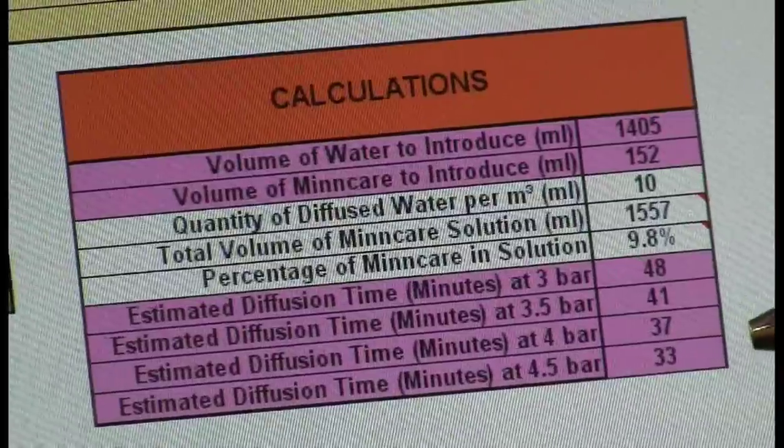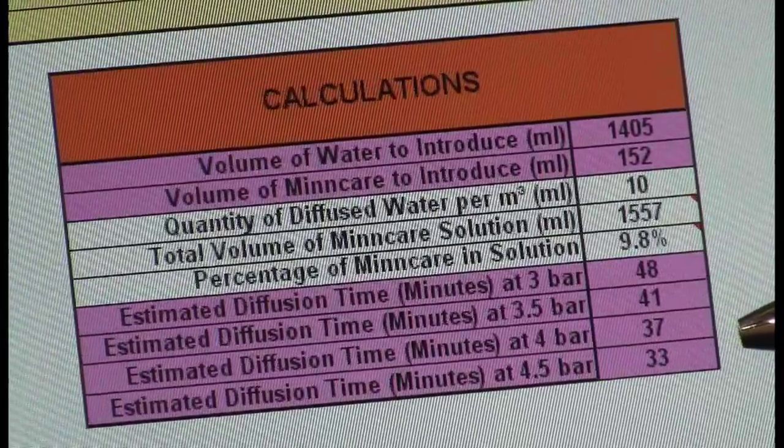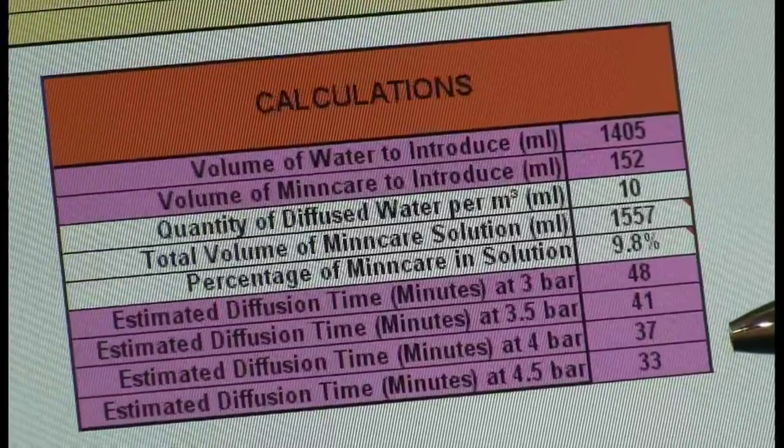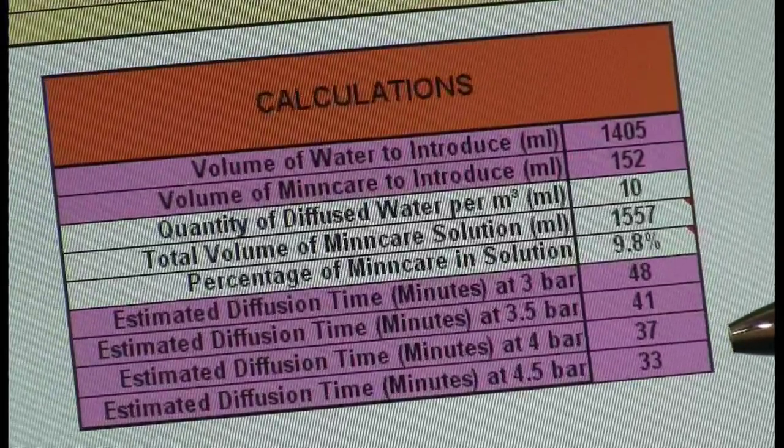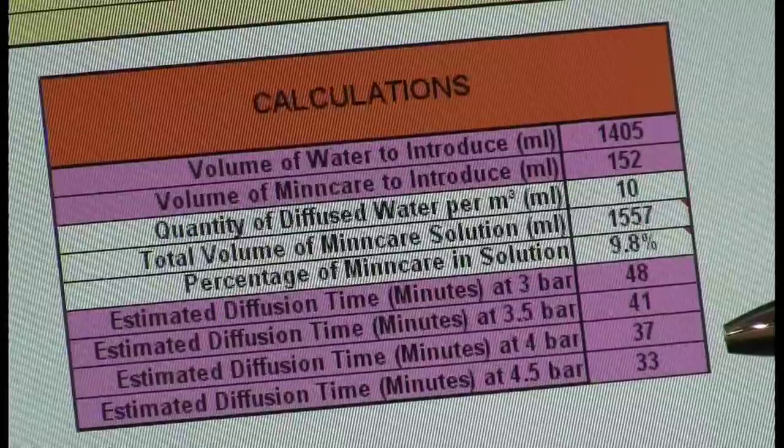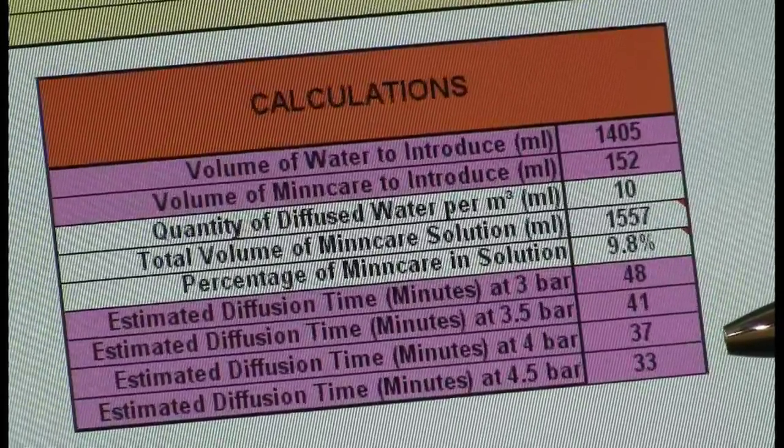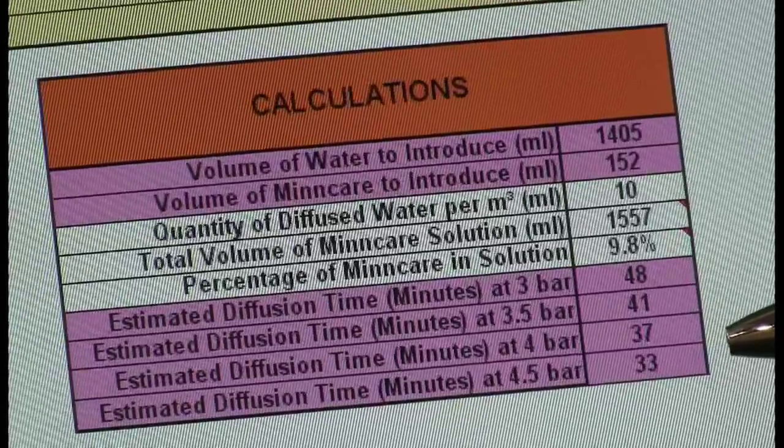Input your number of nozzles right here and that will tell you exactly how much water to introduce, how much MinCare to introduce and at 4.5 bar, which is 65 PSI, it'll take you 33 minutes to completely disperse the dry fog into your clean room. The only other thing you need to know is you need 2.5 SCFM per nozzle for the Markor dry fog machine.